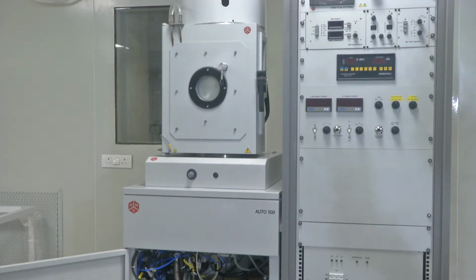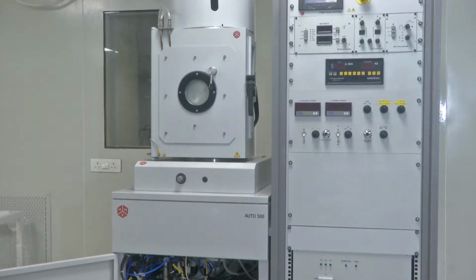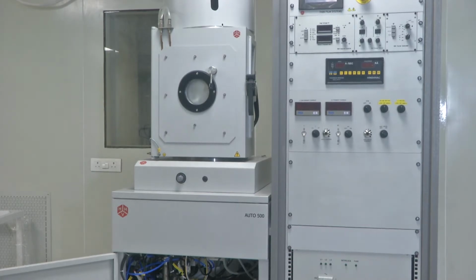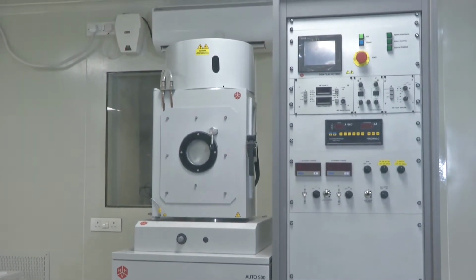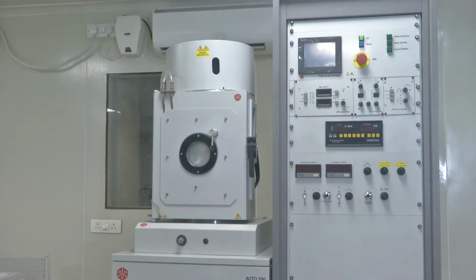Close the backing valve and open roughing. Wait until the chamber reaches better than -2. Then after reaching -2, close the turbo roughing valve and open backing. Then open the high vacuum valve. When the high vacuum valve is opened, the turbo will be connected to the chamber and start working. Then high vacuum of -5, -6 starts. How much time will this system take to reach -6? About 1 hour.